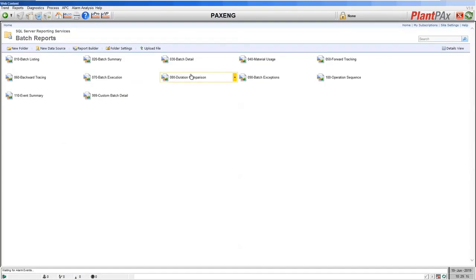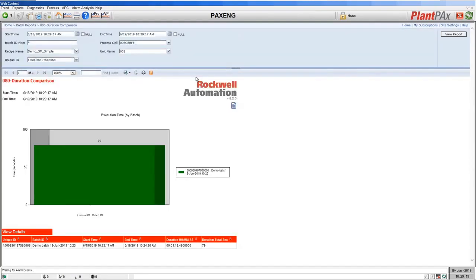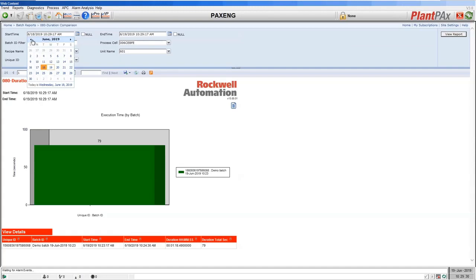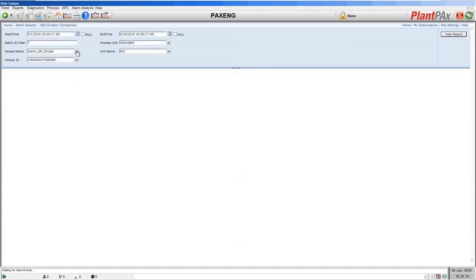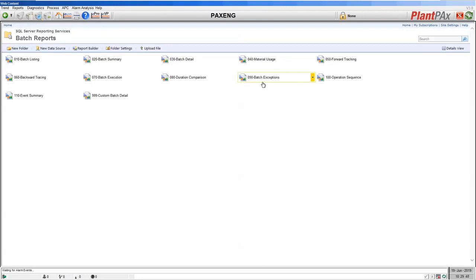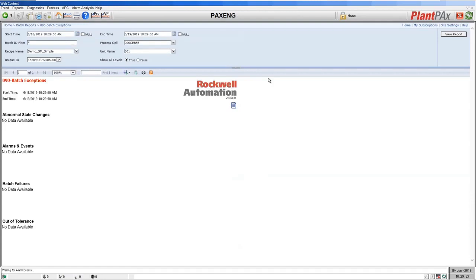The next report is the duration comparison report, which is all about comparing executions of different sequences. In the last 24 hours we've only run one sequence, but we can go back to earlier time and select previous executions to compare them. Next is the batch exceptions report — this covers any failures that occurred when running the batch. If a failure had caused the Sequence Manager sequence to go into hold, or we had manually put it into hold, that would be shown here. There were no failures, so there's nothing to show.